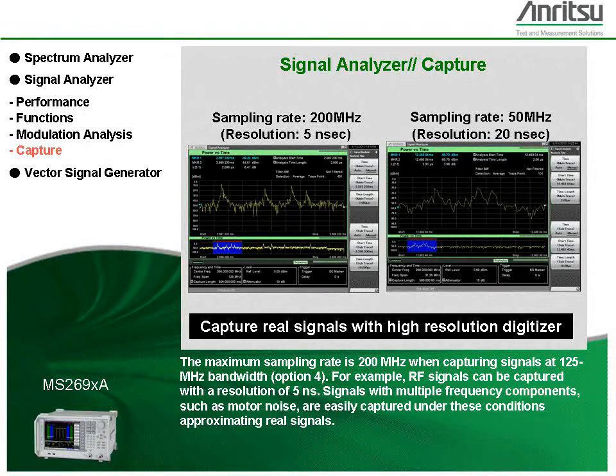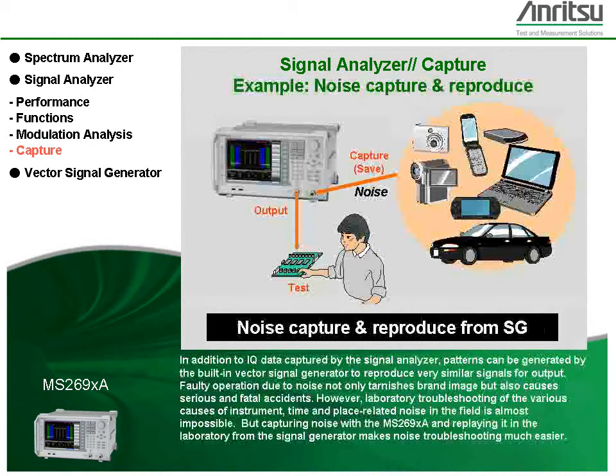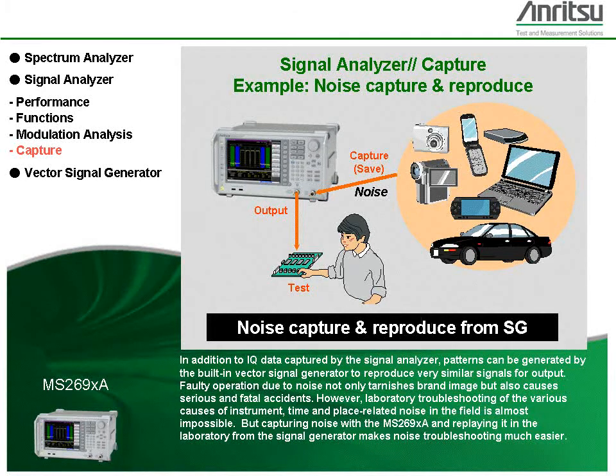Signals with multiple frequency components, such as motor noise, are easily captured under conditions approximating real signals. In addition to IQ data captured by the signal analyzer, patterns can be generated by the built-in vector signal generator to reproduce very similar signals for output. Faulty operation due to noise not only tarnishes brand image but also causes serious and fatal accidents. Capturing noise with the MS269XA and replaying it in the laboratory from the signal generator makes noise troubleshooting much easier.